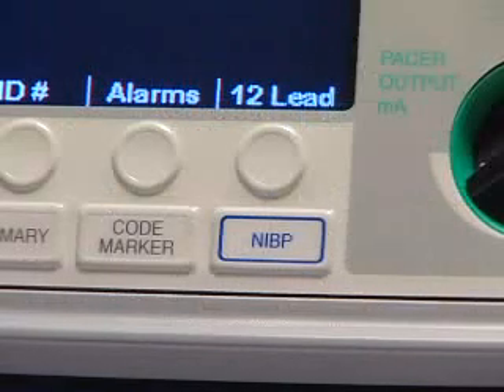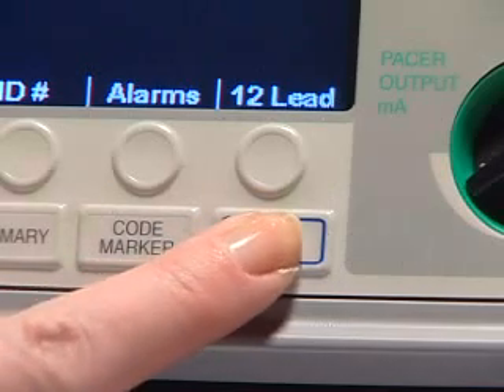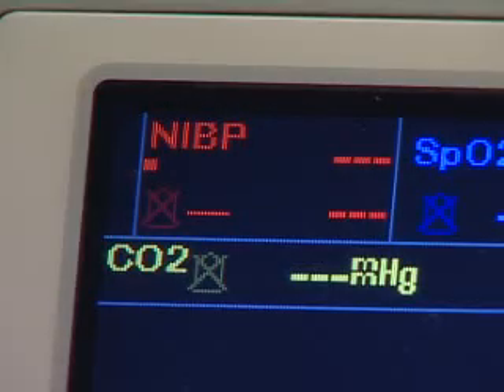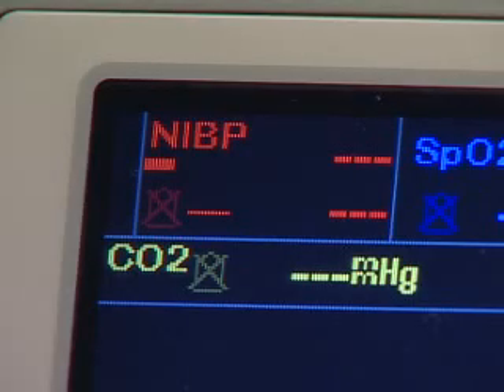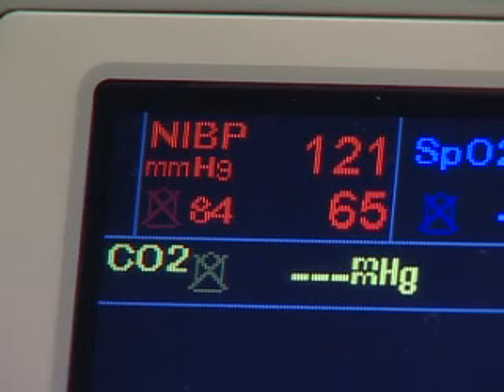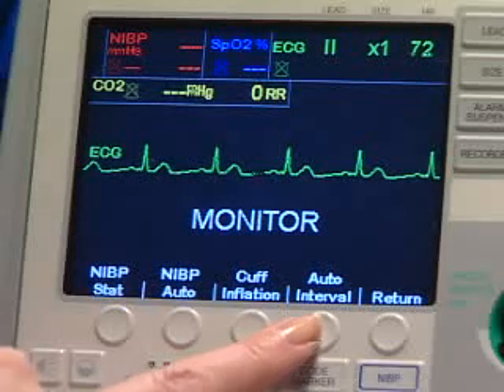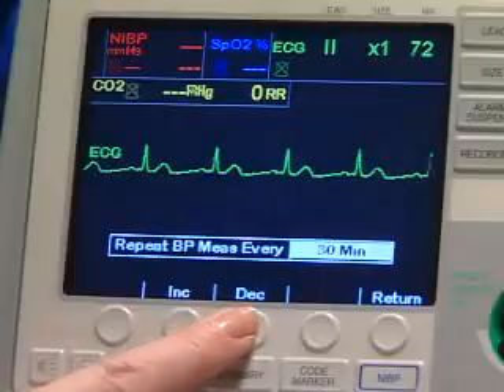To take a single measurement, press the NIBP button. The cuff inflation bar reflects the status of the cuff inflation pressure. This cycle takes approximately 30 seconds. The E-Series will not start a new measurement unless 10 seconds have elapsed since the end of the previous completed measurement cycle. To take an automatic measurement, first select the appropriate interval.